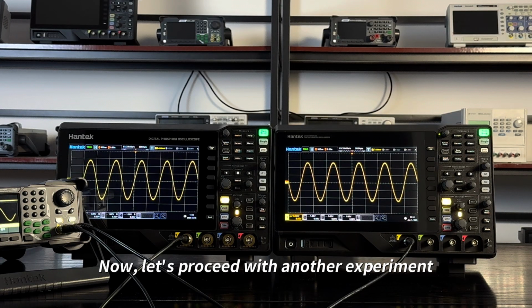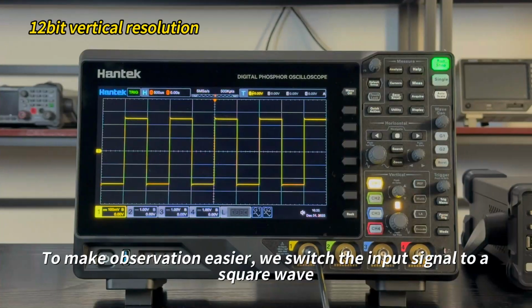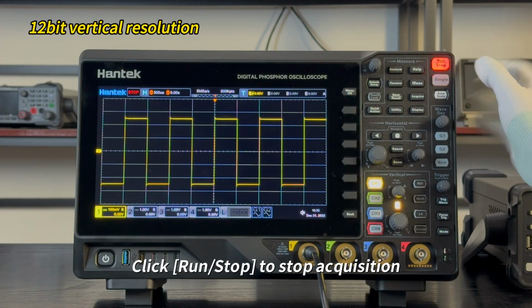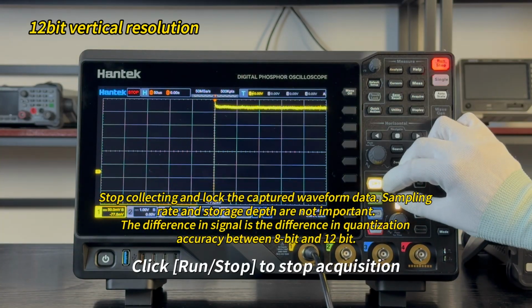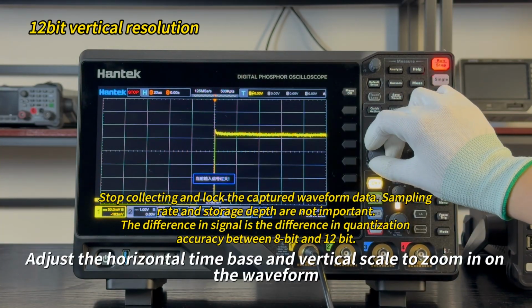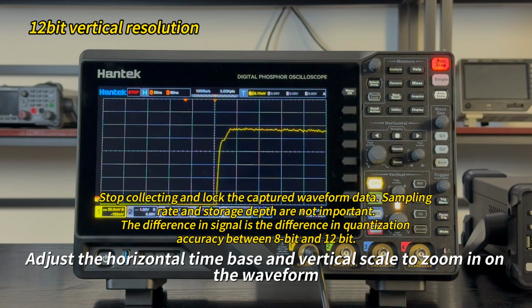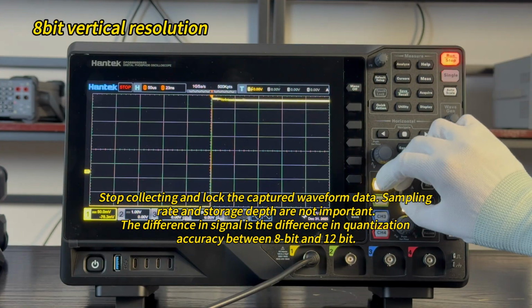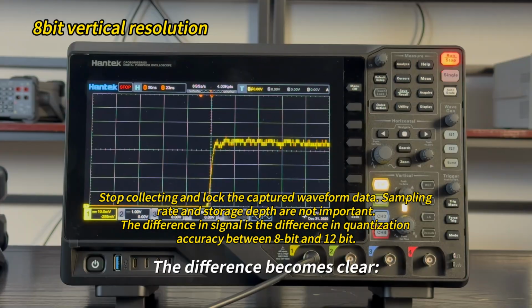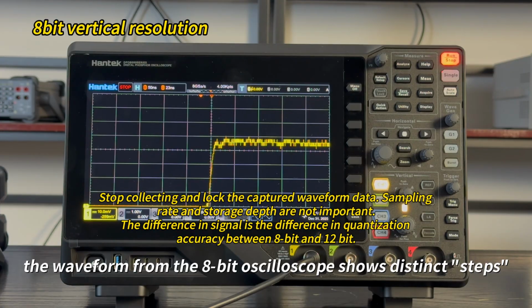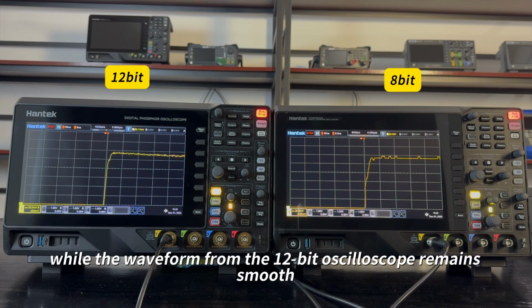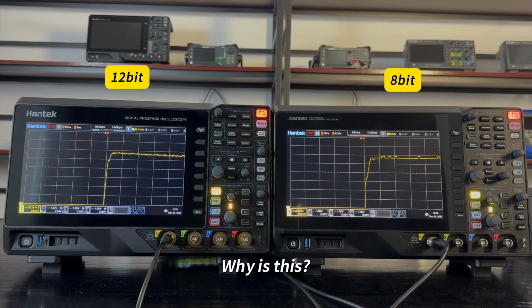Now, let's proceed with another experiment. To make observation easier, we switch the input signal to a square wave. Click Run Stop to stop acquisition. Adjust the horizontal time base and vertical scale to zoom in on the waveform. The difference becomes clear. The waveform from the 8-bit oscilloscope shows distinct steps, while the waveform from the 12-bit oscilloscope remains smooth. Why is this?